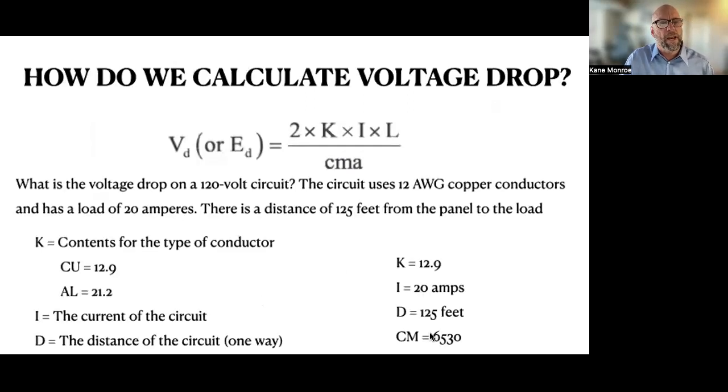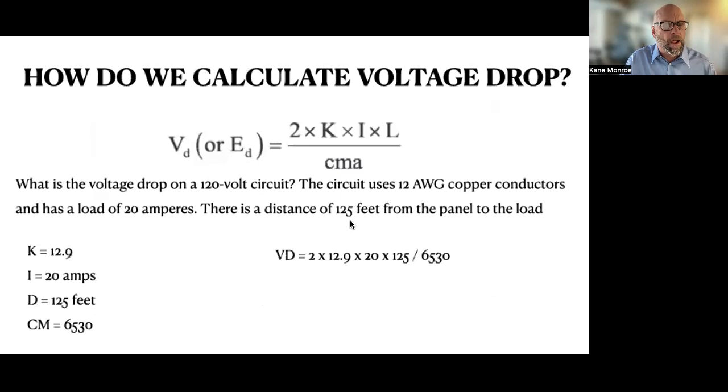So we plug that. We can plug 6530 into our formula. And it looks something like that. Two times K, which is 12.9 times 20, which is our current times 125, which is our distance, our length divided by 6530. So you multiply all that out, you get 64,500 divided by 6530.